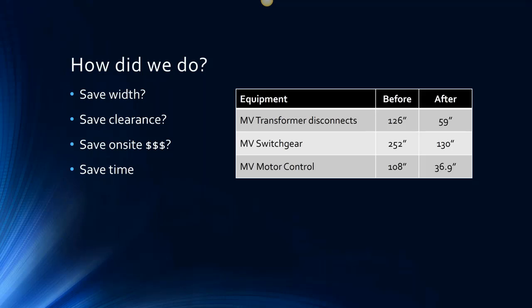So looking back on our electrical room and our endeavor, how did we do? Did we save ourselves some width and therefore save us some dollars? Well, our medium voltage transformer disconnects, we went from 126 linear inches to 59 inches. On our medium voltage switchgear, on the option we chose, we went from 252 inches to 130 linear inches.